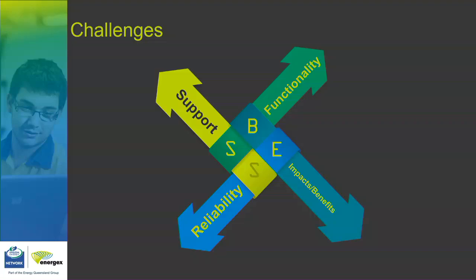And the other challenge with it is the operation of the battery changes from month to month, from season to season. We've got a couple of battery systems, we're logging onto them every 3 months and changing the set points in them, because the voltage through summer on the feeder might sit a little bit higher with all the solar, less load through winter when everyone's turning the heaters and everything on, the volts drop a little bit. And because the battery's responding to that, we've got to change its set point. So it's a dynamic interaction we have with the battery systems through the year.